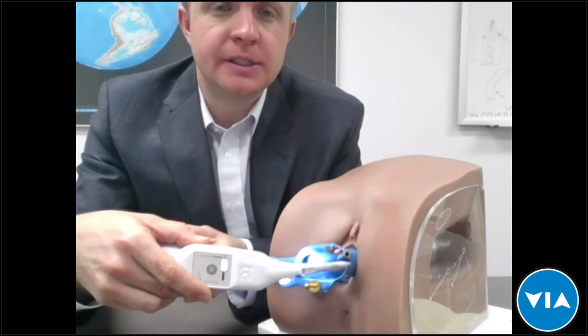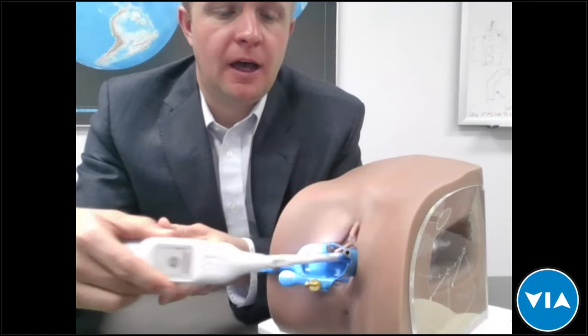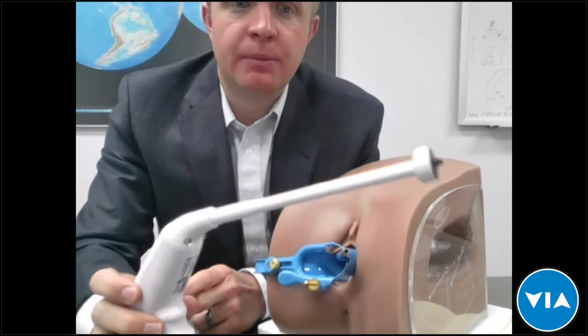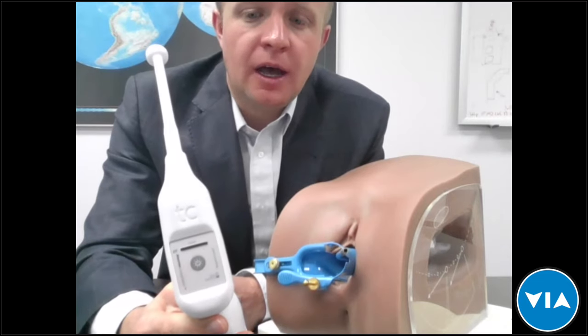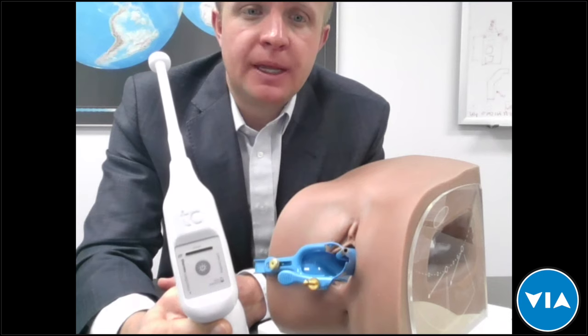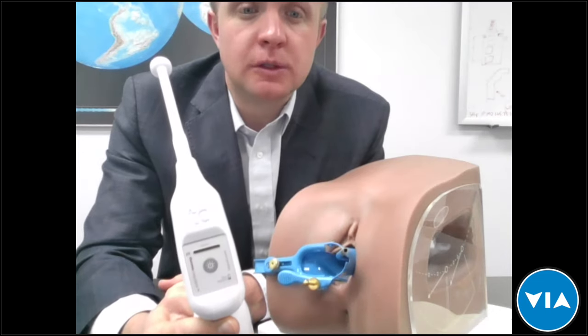It's halfway through now. The standard treatment is 100 degrees Celsius for 30 seconds, and that can be modified to 45 or 60 seconds, with a choice of 100 or 120 degrees Celsius. The device also has examination lights — it's a very simple, single-button operation by design. It's used by doctors, midwives, and people trained by doctors and midwives, which is why it couples very well with screen-and-treat programs where clinicians do the visual inspection with acetic acid.